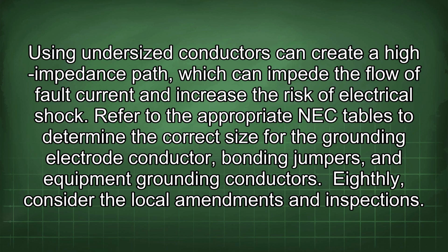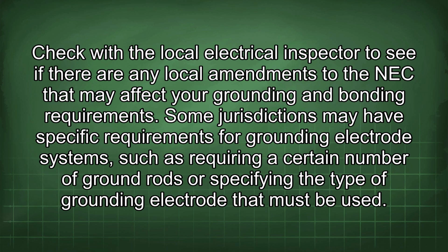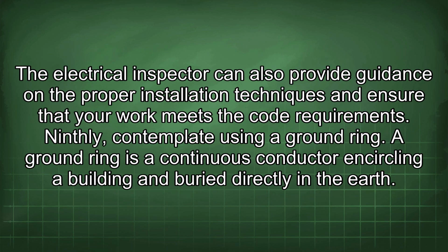Eighthly, consider the local amendments and inspections. Check with the local electrical inspector to see if there are any local amendments to the NEC that may affect your grounding and bonding requirements. Some jurisdictions may have specific requirements for grounding electrode systems, such as requiring a certain number of ground rods or specifying the type of grounding electrode that must be used. The electrical inspector can also provide guidance on the proper installation techniques and ensure that your work meets the code requirements.